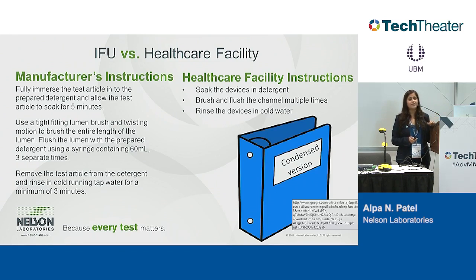place? So what I have seen recently is that these IFUs have a condensed version of them, which the healthcare facilities make, and they're very short. Like you can see here, soak the devices in detergent, while the first step has fully immersed the test articles into the prepared detergent and allow the test articles to soak for 5 minutes. So very short, very concise. Of course, in your IFU, you have to write it step by step, but this is what the healthcare facilities are doing at this point. It's in a binder. There's probably 8 cleaning instructions in there, and they're using those instructions to clean the medical devices.